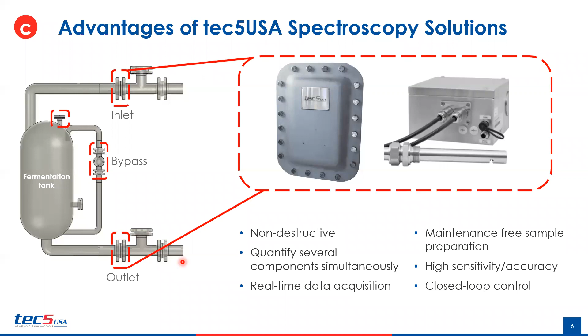So although laboratory measurements are performed with high sensitivity and accuracy, you can achieve similar sensitivity and accuracy with near IR spectroscopy in real time. And then finally, the one final advantage is the ability to have closed loop control. Ultimately, the decisions that are made from the results can be set up to be automated if the end user chooses to do so. So either manual decisions and manual actions being made off of these results, or automated control, is also a possibility.